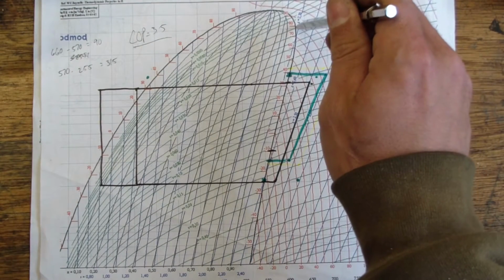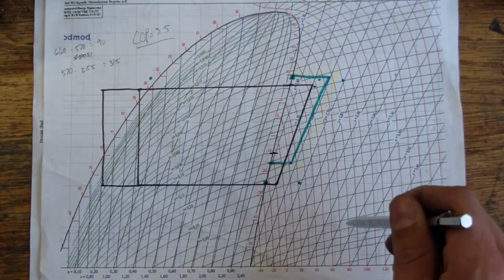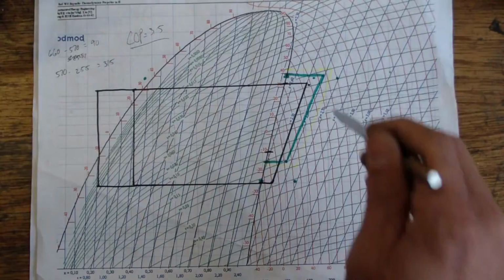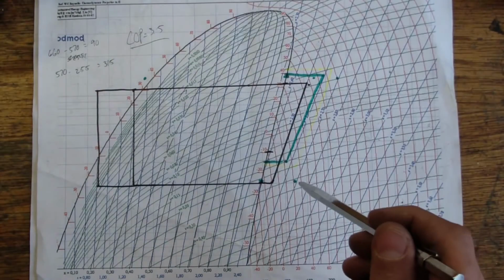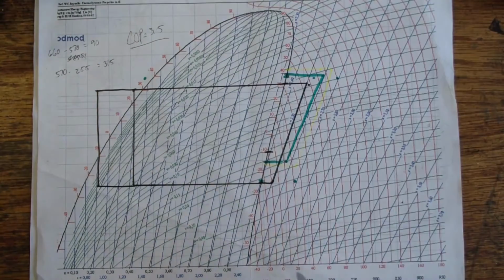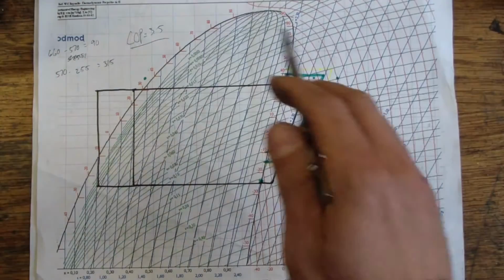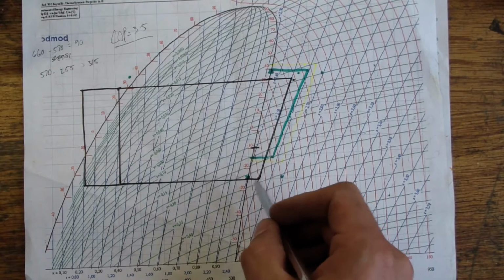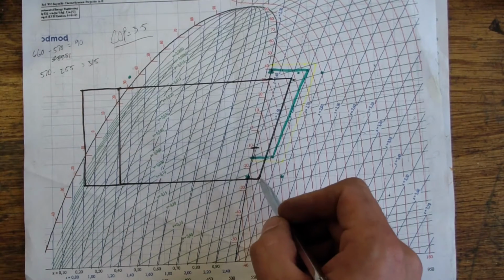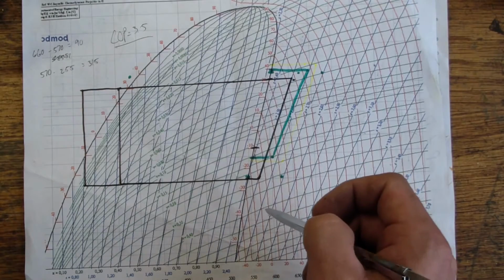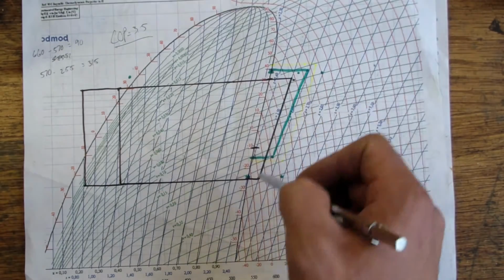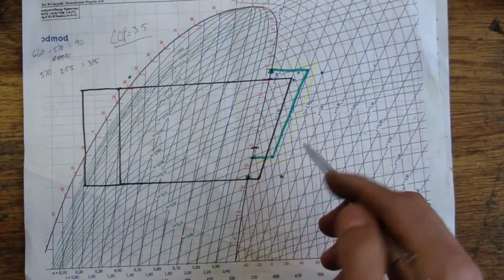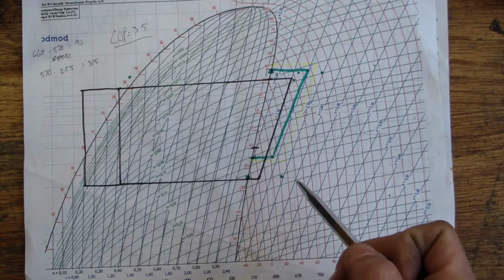So the temperature here is 80 degrees C, the temperature here is 80 degrees C. But what changes across that isothermal is the pressure. It changes the specific volume, it changes the entropy, and all those things. So we're looking at all these different characteristics and the way they interplay. So we have a superheated gas that enters into the compressor. The compressor draws it into the cylinder and compresses it. Now, during that compression, we know obviously the increase in pressure because we're going vertically on the chart, but we also increase in temperature as well.